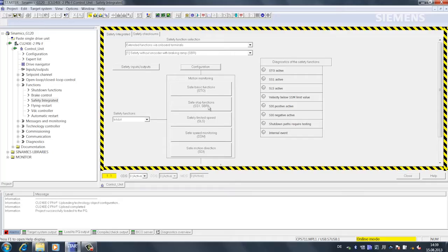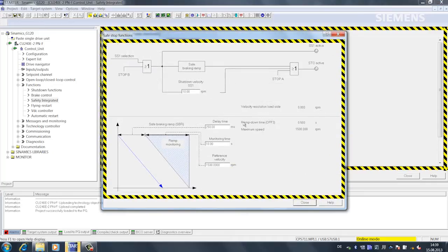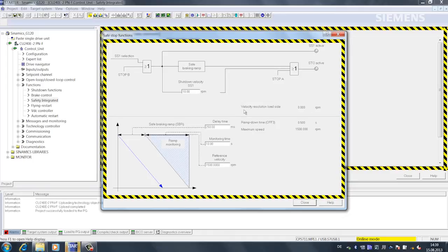We specify which ramp is to be monitored in the SS1 settings. This is normally set in the same way as OFF3. I'll change the monitoring time to 0.5 seconds.